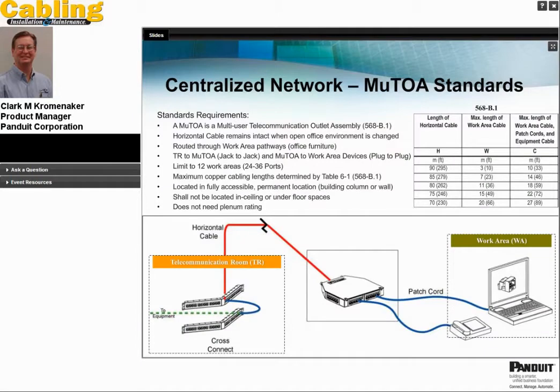So MUTOA standards. MUTOA, Multi-User Telecommunications Outlet Assembly, is codified in TIA 568B.1. The horizontal cable remains intact when the open office environment is changed, so we're talking about the horizontal trunk cable per the image below. It can be routed through work area pathways through the office furniture, or in some instances the cable just lays open going to the actual computer or device. The telecommunication room to MUTOA is jack to jack, and the MUTOA to work area device is plug to plug.